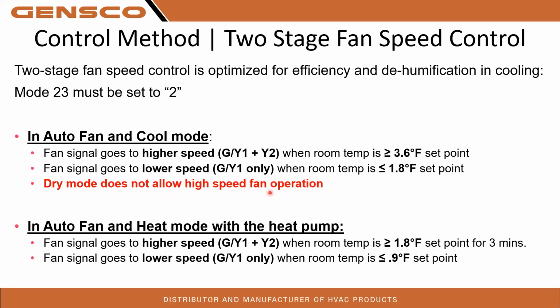Dry mode does not allow a high speed fan operation. It will only run the low speed if you're running a two-stage furnace. In dry mode, we don't want to overshoot the room. We just want to try to pull out some of the humidity in there. So high fan speed is not wanted and not an option. And heat mode in auto fan, same kind of principles there. If we see more than or equal to 1.8 degrees from set point for 3 minutes, it'll switch to high speed fan. Once it gets down to equal to or less than 0.9 degrees from set point, it'll switch back to the low speed fan.